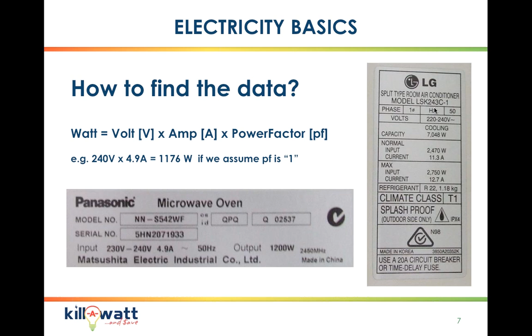The only exception to the rule is for air conditioning, where cooling capacity is also measured in watts or kilowatts. What you're looking for here is the item that says the input current. So max input current is 2.7 kilowatts or 2,750 watts. That's what this unit will consume if it was running at full mode for 1 hour. So that gives you an idea of how much that unit would cost to run.